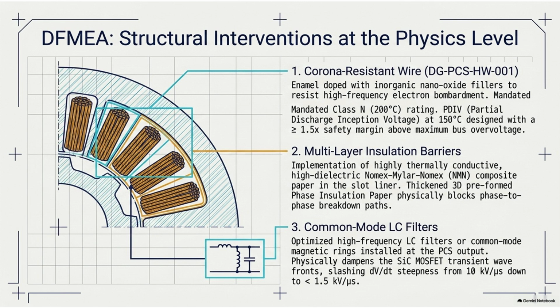Which brings us to the design phase. The DFMEA, or Design Failure Mode and Effects Analysis. Right. This is where they try to build the physical fortress. How do engineers design a motor so those four forces of degradation, the heat, the sparks, the rubbing, the salt, just can't win? They attack the vulnerabilities at the absolute microscopic level, and they start with the copper wire itself. You cannot use standard industrial copper wire in an EV motor. It wouldn't survive a day.